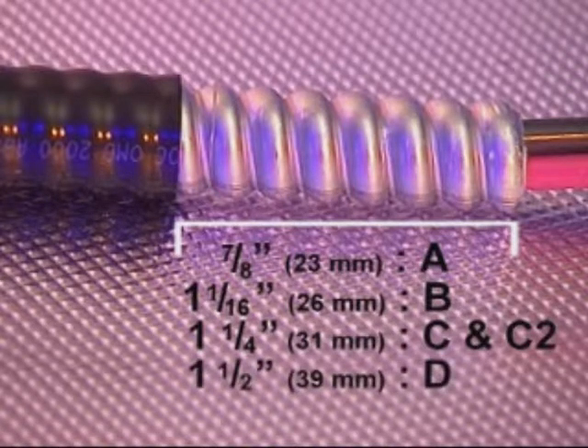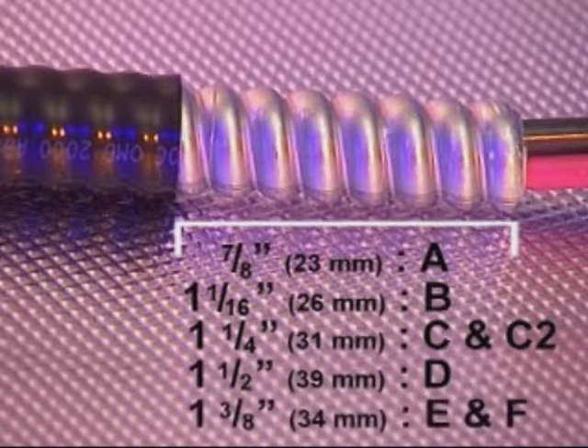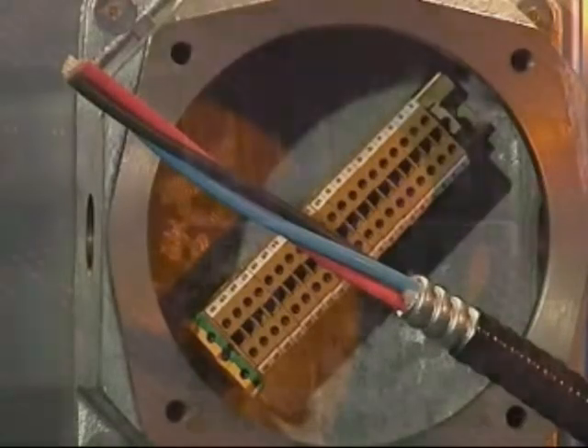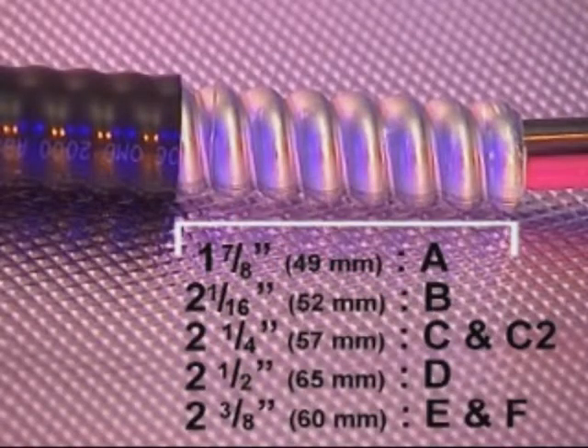For C and C2 size cable glands, remove 1 and a quarter inches (31mm). For E and F size cable glands, remove 1 and three eighths inches (34mm) of the outer sheath. For the 701, the cutting length for removal of the outer sheath should be 1 inch (26mm) longer. As a rough guide, the outer sheath should be removed in line with the edge of the grounding device.